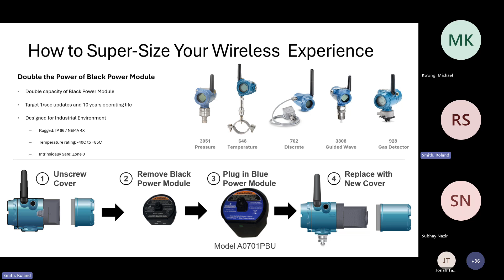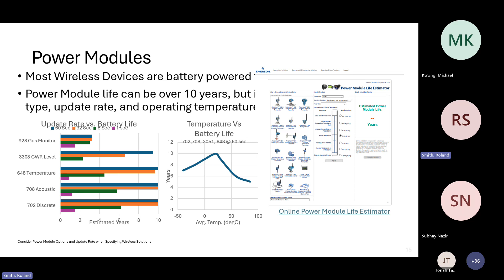We have an online estimator. A very common question we get is how long our power modules will last, so we have an online estimator to help with that. Burst rate or update rate plays a key part, as well as ambient temperature. In northern climates we can enter an average ambient temperature of, say, 0 degrees Celsius into the calculator, along with the update rate. You can see the difference even on our 702 discrete, the bottom one here—at a 1 minute rate we get an 8 to 10 year life. As the burst rate gets more frequent, we drop down to under about 2 years for a power module, which is still pretty good, but that can directly affect the power module's life expectancy.